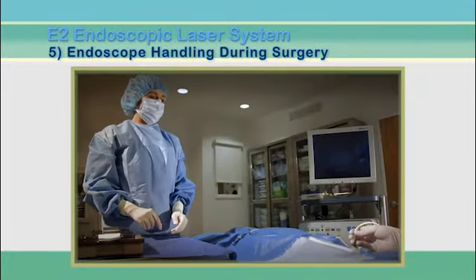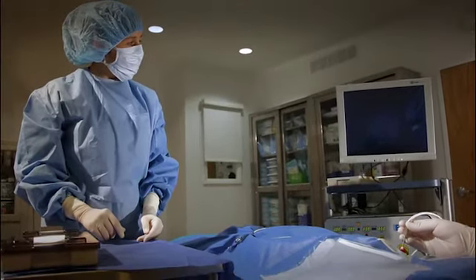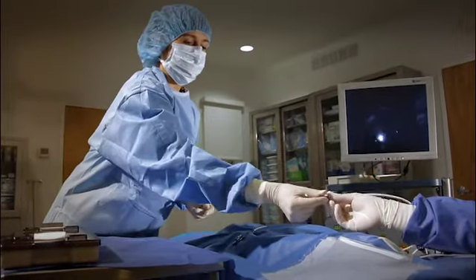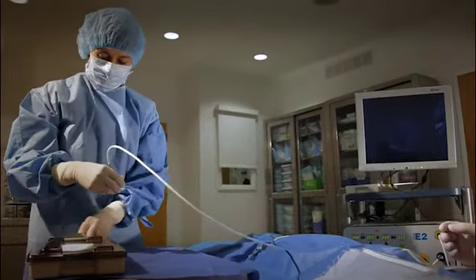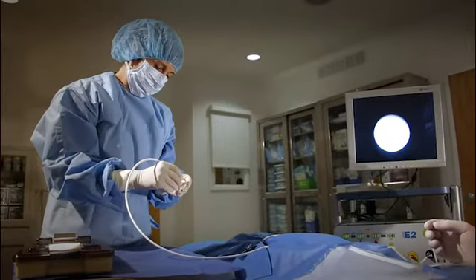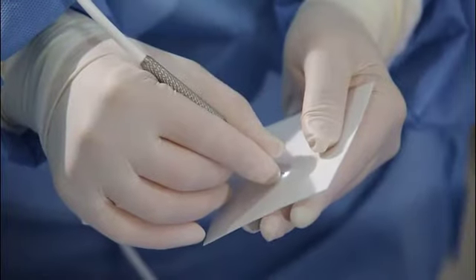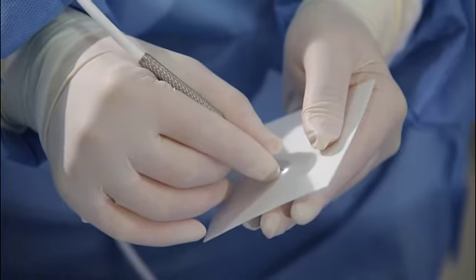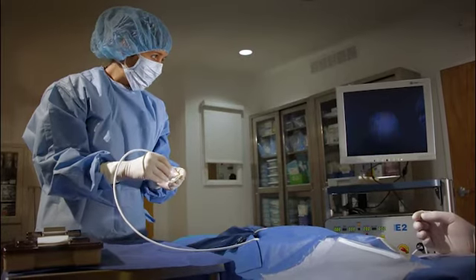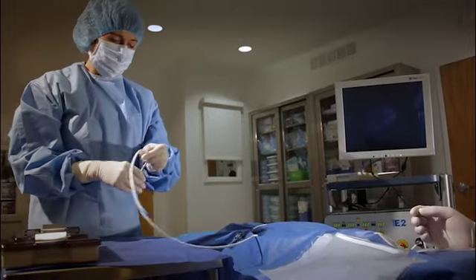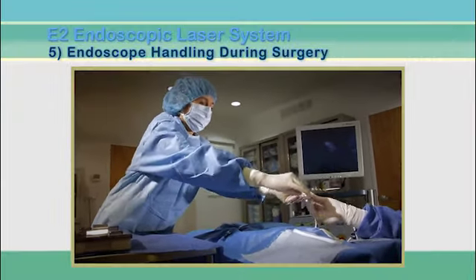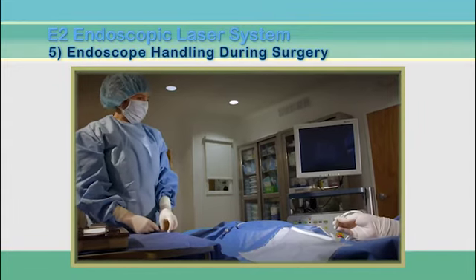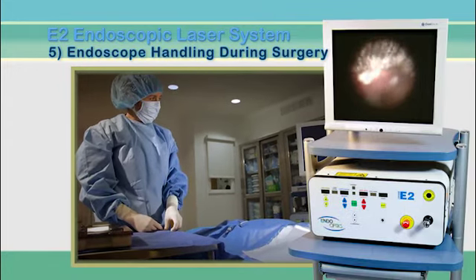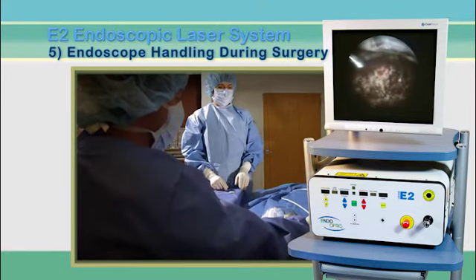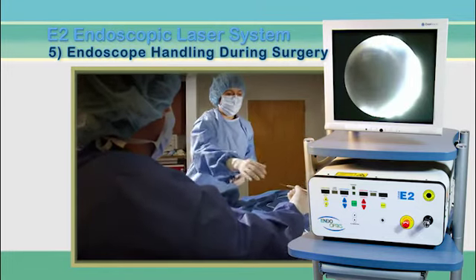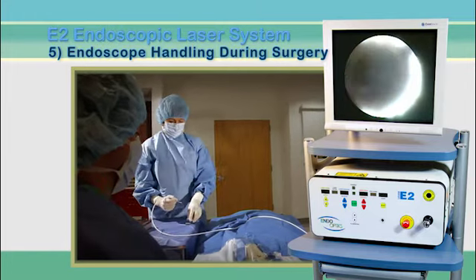As surgery proceeds, the flat surface of the cannula, known as the tip, may become dirty. It is important for the scrub nurse to keep the tip of the endoscope clean during the procedure. Do this by holding the cannula close to the tip and gently swabbing with a wet instrument wipe to fully clean any viscoelastic or other materials from the surface. If the tip is clean, the image on the screen will be clear and in focus. When the surgeon is finished with the endoscope, the tip should be wiped again in the same way and the image inspected for clarity.